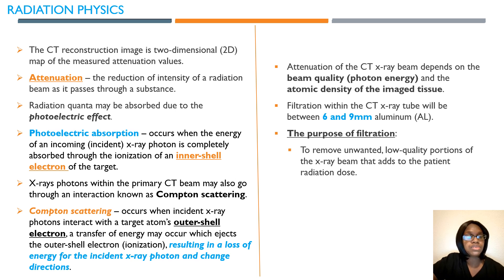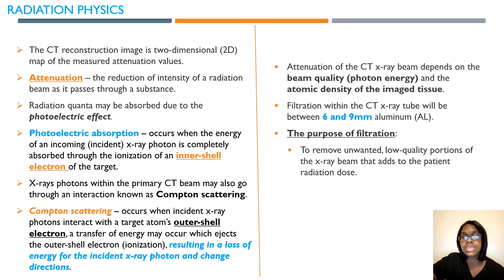X-ray photons within the primary beam may also go through Compton scattering, which is whenever an incident x-ray photon interacts with an outer shell electron. This results in a loss of energy from that incident x-ray photon because it changes directions. Also remember that the filtration within the CT x-ray tube is going to be between 6 and 9 millimeters aluminum. The purpose of filtration in CT is to remove unwanted low-quality portions of the x-ray beam that add to the patient radiation dose.